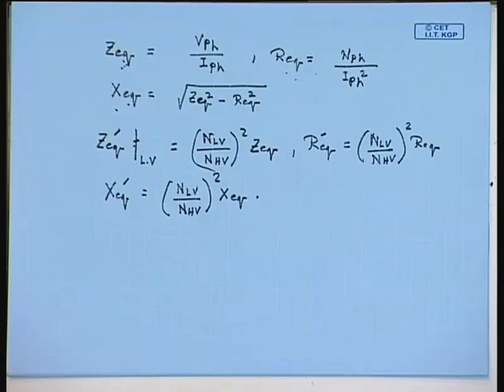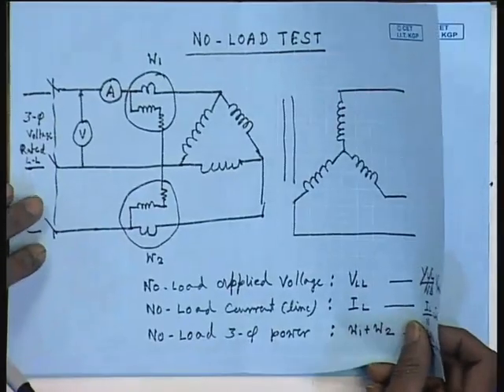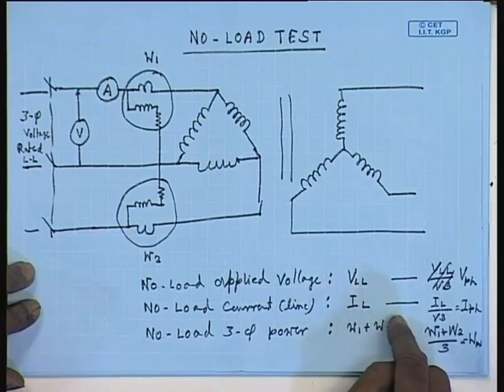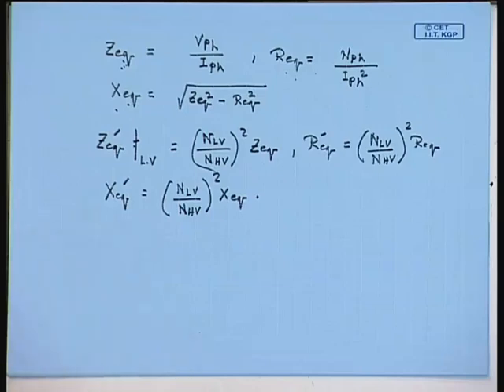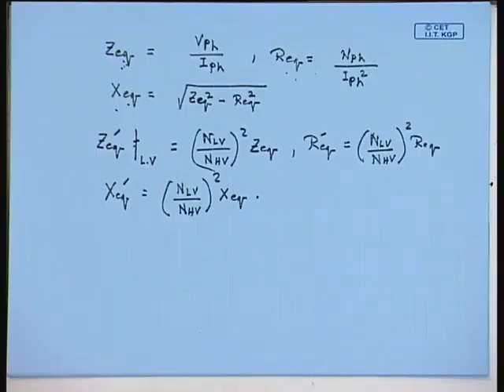In fact, the test data in themselves are sometimes specified in per unit terms. That is, when you are doing no load test, you can say that we applied 1 per unit line to line voltage. So, the line current was so many per units and the 3-phase power was so many per units. It can be easily shown that if the test data themselves are specified in per unit form, then the parameters that we will determine from the test data will also be in per unit, in which case this referring to different sides will not be necessary.